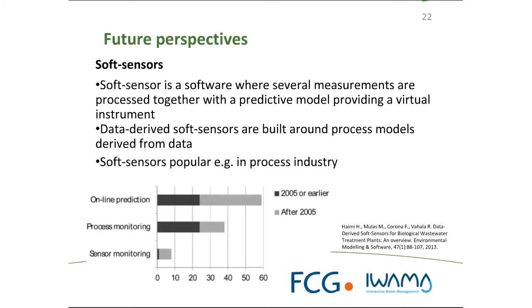One example, and this is about Viikinmäki wastewater treatment plant in Helsinki, post-filtration process where denitrification takes place. There's methanol dosed in this process as an external carbon source, and methanol dose is controlled by nitrate measurements in all of these different filter cells. So we designed soft sensors which estimate nitrate concentrations in these filters. And these estimates were quite successful. Prediction error was smaller than the error of hardware instruments. And in this kind of case, we could use these software sensor estimates for controlling the process, in this case controlling methanol dosage. For instance, when there are situations that the instrument signal is not available because of maintenance or some error.